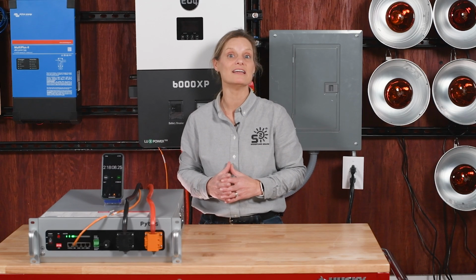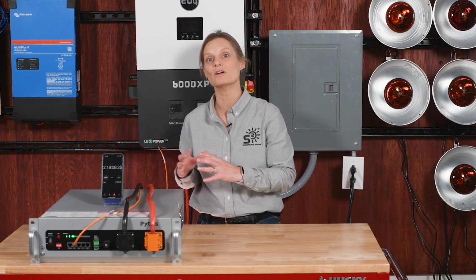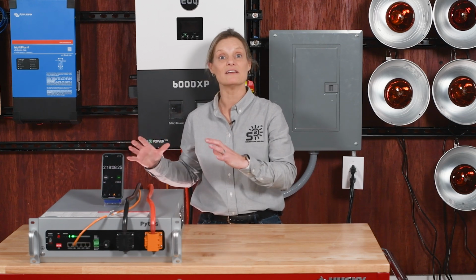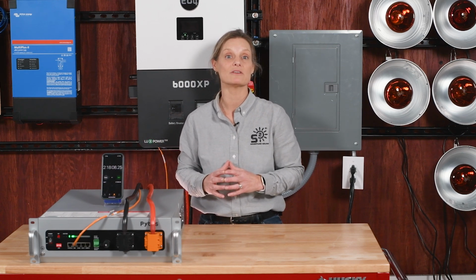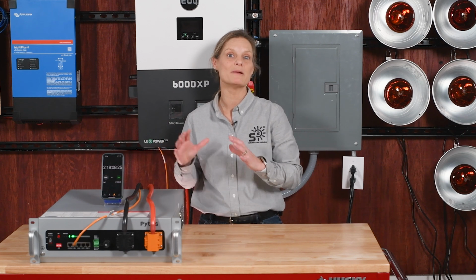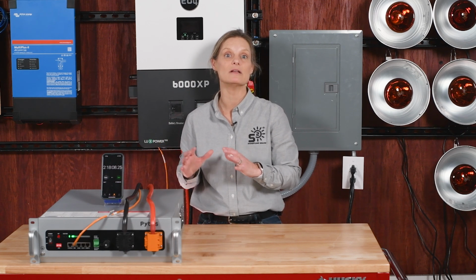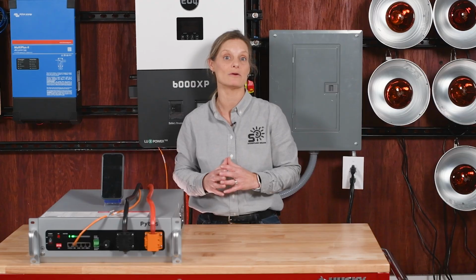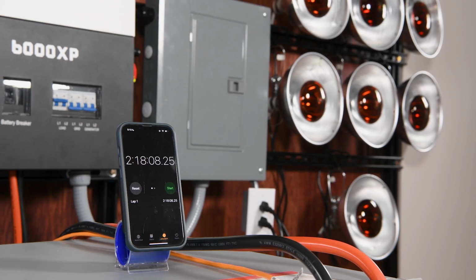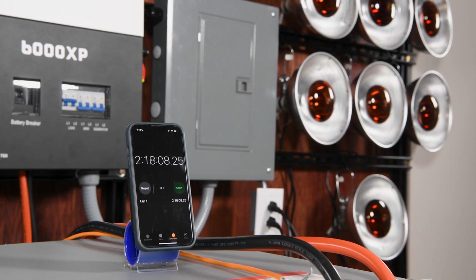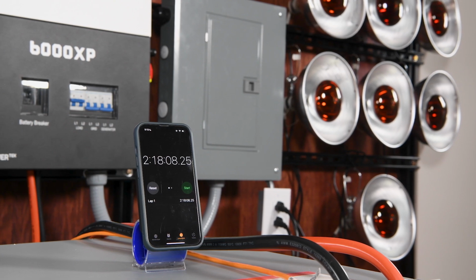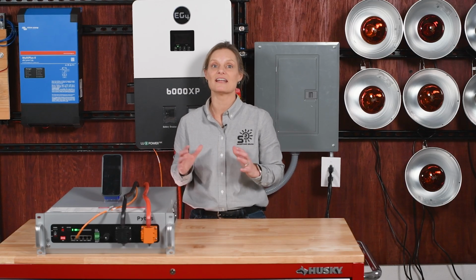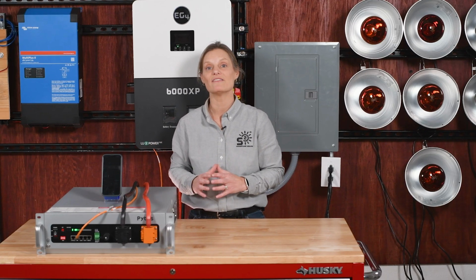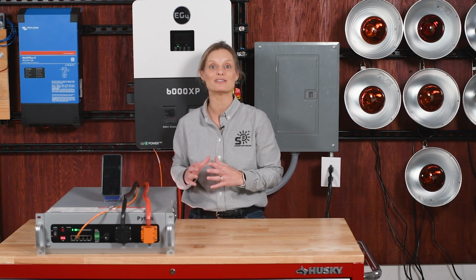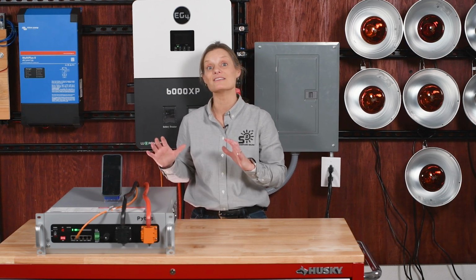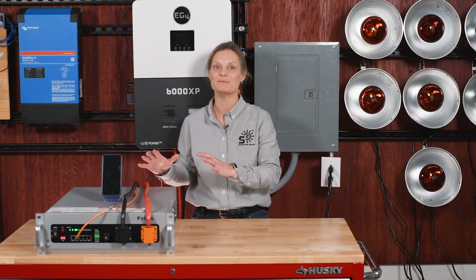If we recalculate 90% of the battery's 5.12 kilowatt hour capacity, that gives us 4.61 kilowatt hours. Dividing 4.61 by 1.84 yields an estimated runtime of about 2.5 hours. Here we see that we were able to run this load for 2 hours and 18 minutes. This load test not only gives us an estimate of how long the Pytes V5 can sustain a load at just under 2,000 watts, but it also highlights the safety features built into the battery's BMS.